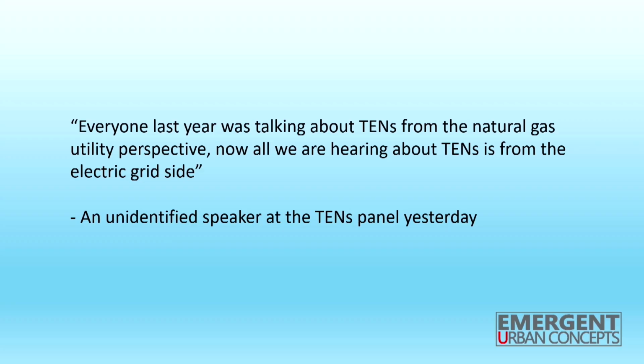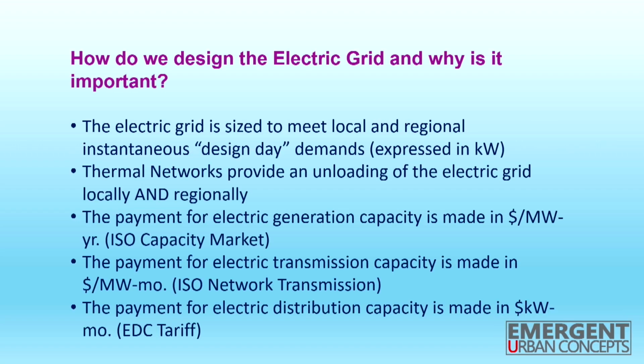So what's the grid side measured in? It's measured in kW and in kWh. So how do we design the electric grid and why is it important? Well, the electric grid is sized to meet local and regional instantaneous design day demand, expressed in kW, or MW, megawatts.